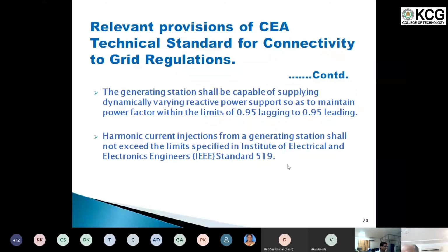Of course, nobody is providing any extra capacity inverter, for the simple reason that most of the time you are not operating your inverters at full capacity, because the sun is not giving you that much radiation all the time. It is during the noon and afternoon time that you get the full radiation. At other times, in any case, it is generating less. And then there are harmonic current injections; inverters are to be designed for this, and it is being done, as per IEEE standard 519. These are the requirements as per the CEA technical standards.